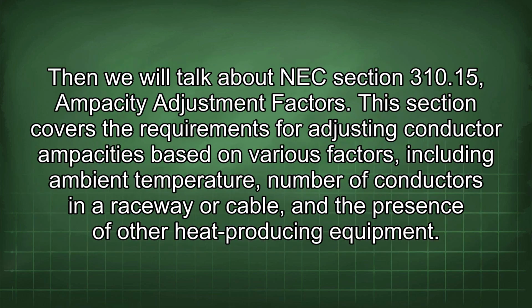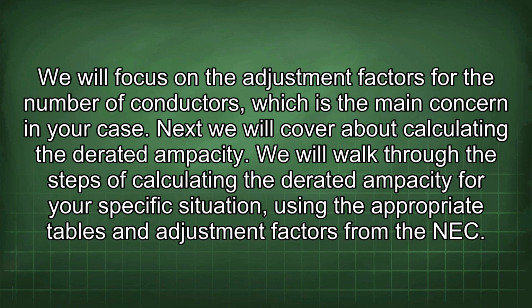Then we will talk about NEC Section 310.15, Ampacity Adjustment Factors. This section covers the requirements for adjusting conductor ampacities based on various factors, including ambient temperature, number of conductors in a raceway or cable, and the presence of other heat-producing equipment. We will focus on the adjustment factors for the number of conductors, which is the main concern in your case.